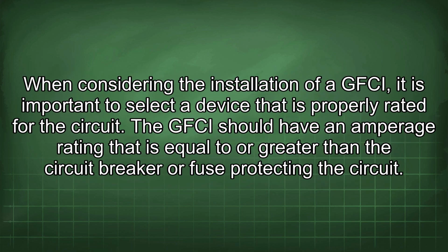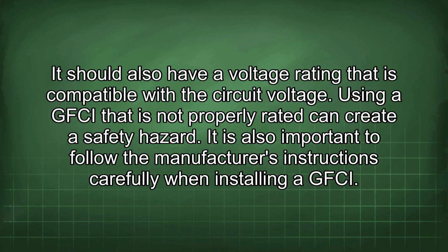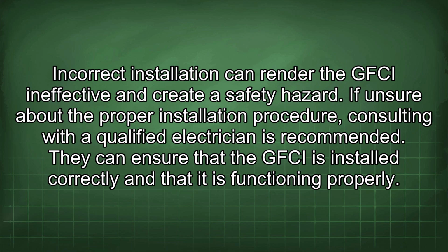When considering the installation of a GFCI, it is important to select a device that is properly rated for the circuit. The GFCI should have an amperage rating that is equal to or greater than the circuit breaker or fuse protecting the circuit. It should also have a voltage rating that is compatible with the circuit voltage. Using a GFCI that is not properly rated can create a safety hazard. It is also important to follow the manufacturer's instructions carefully when installing a GFCI. Incorrect installation can render the GFCI ineffective and create a safety hazard. If unsure about the proper installation procedure, consulting with a qualified electrician is recommended. They can ensure that the GFCI is installed correctly and that it is functioning properly.